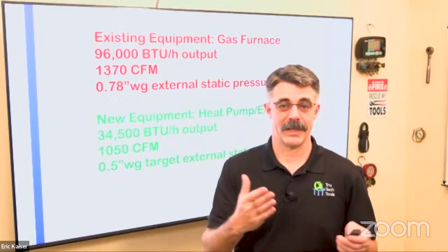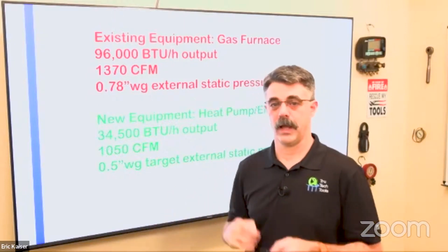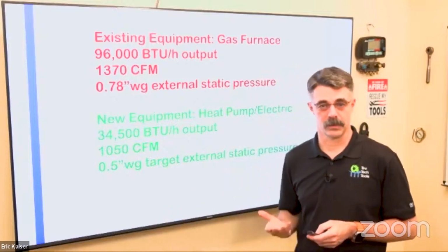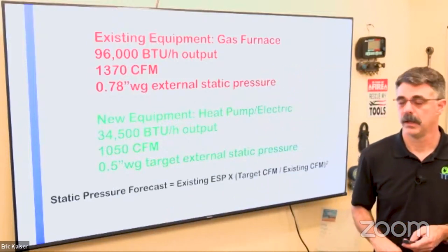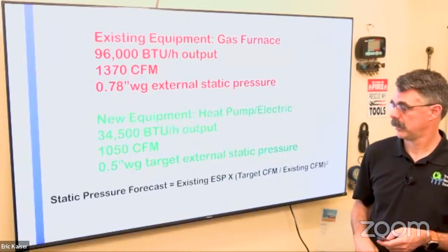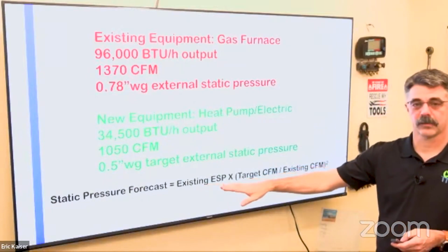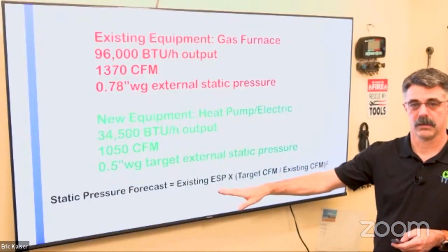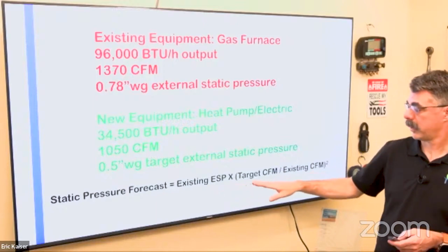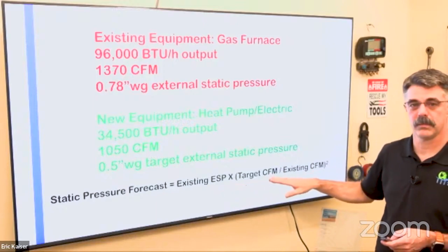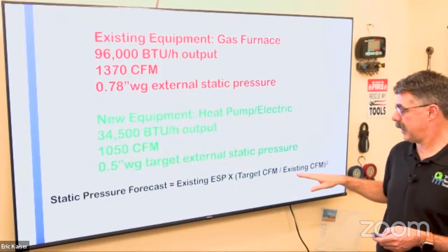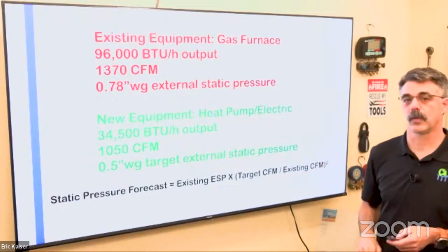So how do we figure out what's happening now and predict what could happen in the future? We're going to use just a little bit of math, all right? And it looks like this. We need the existing external static pressure, or ESP, right? We're going to take the target CFM, divide that by the existing CFM, and square that value.